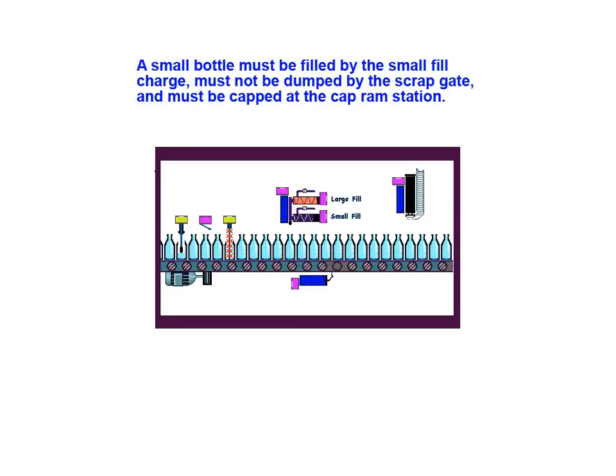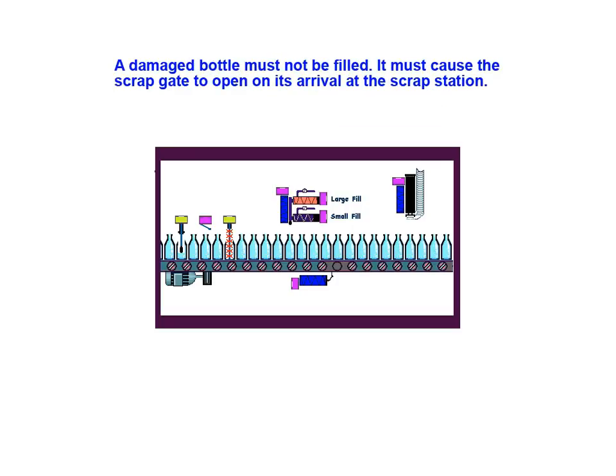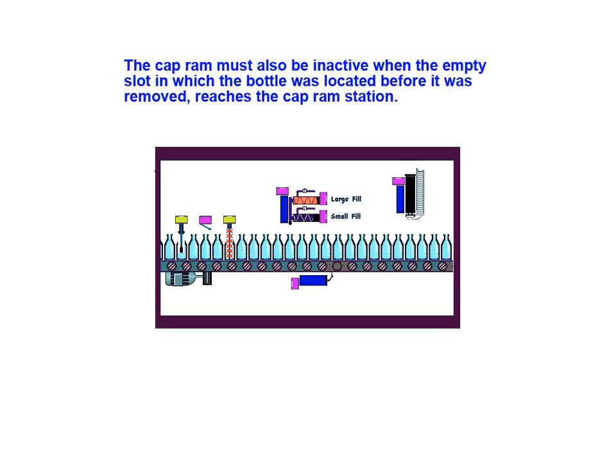A small bottle must be filled by the small fill charge, must not be dumped by the scrap gate, and must be capped by the cap ram station. A large bottle must be filled by the large fill charge, must also not be dumped by the scrap gate, and must also be capped at the cap ram station. A damaged bottle must not be filled; it must cause the scrap gate to open on its arrival at the scrap station. The cap ram must also be inactive when the empty slot in which the bottle was located before it was removed reaches the cap ram station.